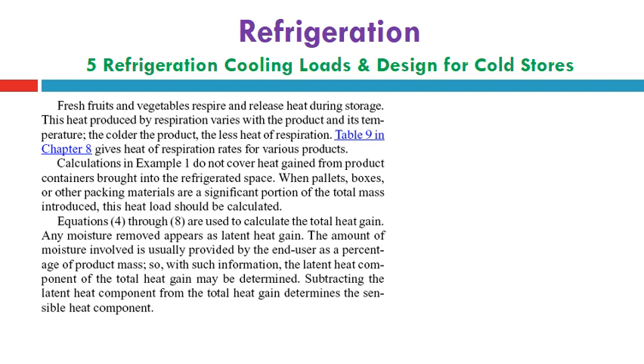All this data you can find in table 3 in chapter 8, which is one of the references of this lecture, from the ASHRAE handbook of refrigeration, to help you during the refrigeration cooling load and design for cold stores.